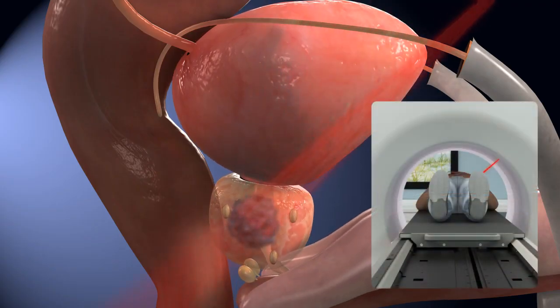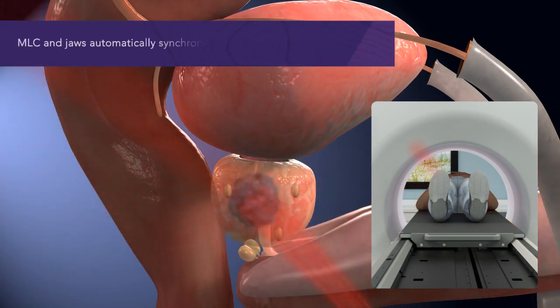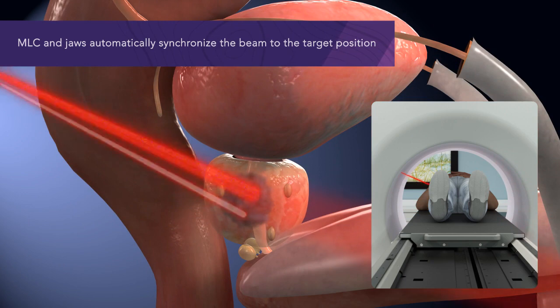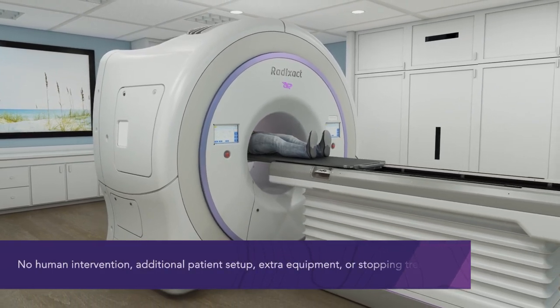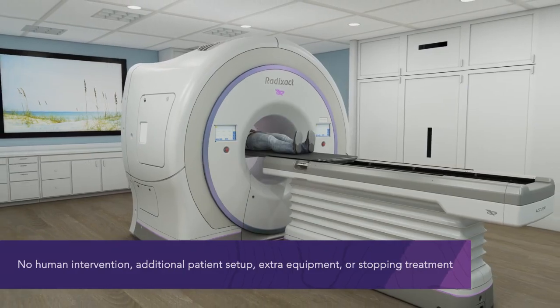During treatment, the KV imaging system tracks and detects prostate movement. The MLC and jaws of the Radixact system correct for the detected movement by automatically repositioning the treatment beam in real time to synchronize it with the prostate's new position — all without human intervention, additional patient setup, additional external equipment, or stopping treatment.